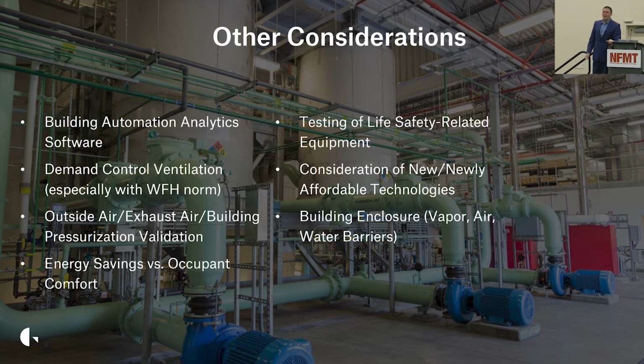Testing of life safety equipment. Take something like stairwell pressurization fans. You don't save any money on those because they never work, but when you need them to work, you want them to work, because we're talking about a fire alarm scenario. You've got smoke in your stairwells because your stairwell pressurization fans haven't been tested for 15 years. This is an important thing to consider.